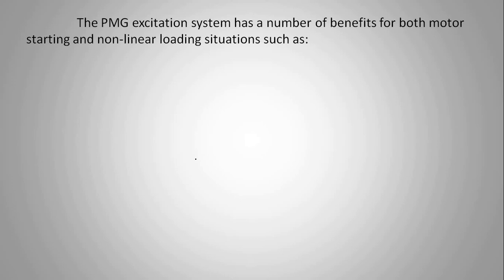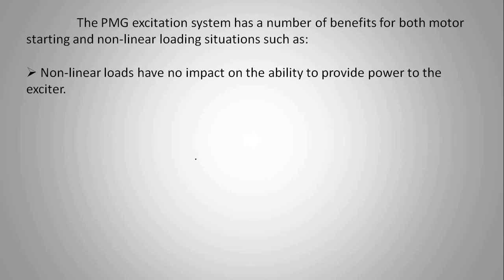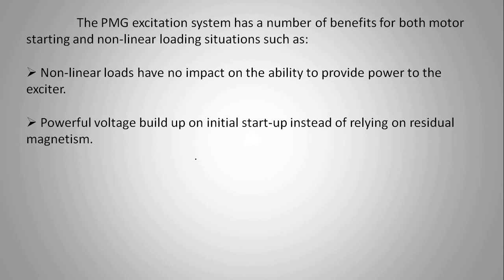This PMG has certain advantages. Those are: the non-linear loads have no impact on the ability to provide the output to the exciter. The exciter gets its input from the AVR, and the AVR input will not be affected by non-linear loads like inductive and capacitive loads, as we discussed earlier. Because of the PMG input source, the AVR will function very well.